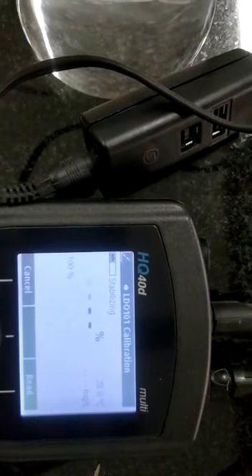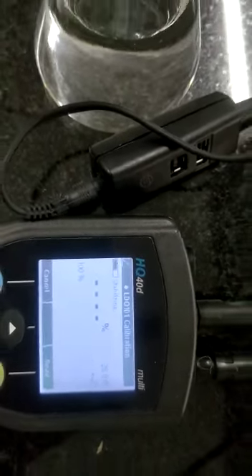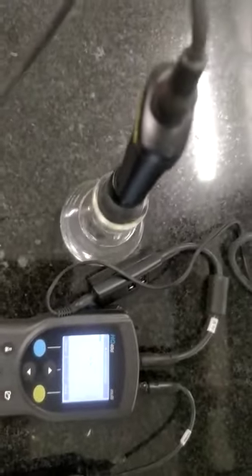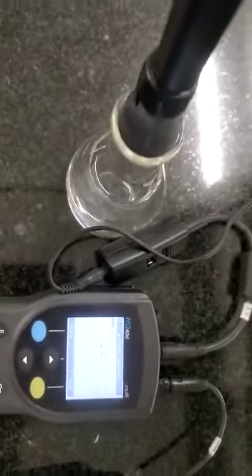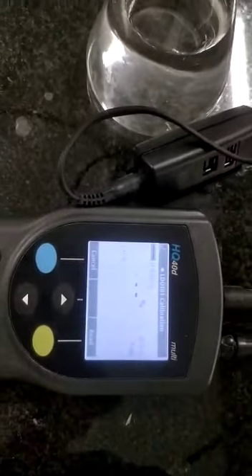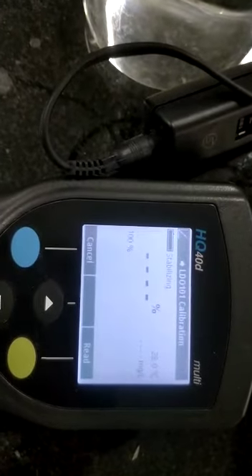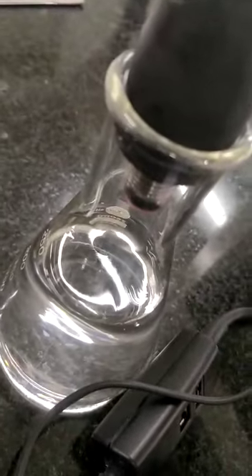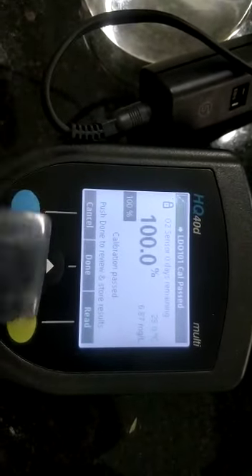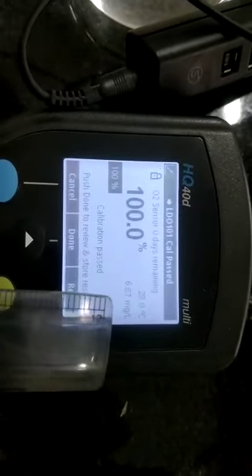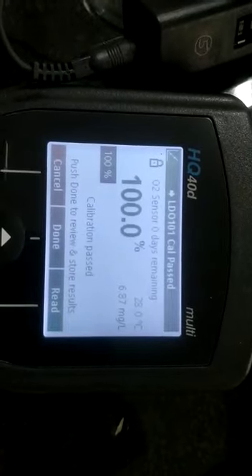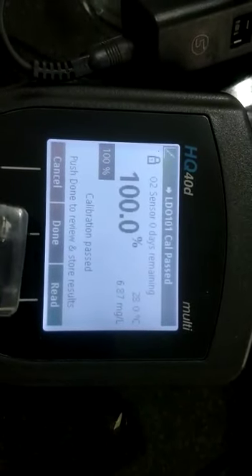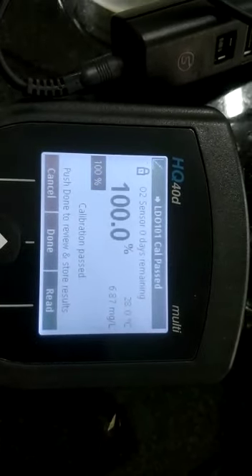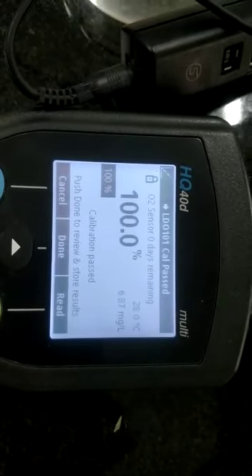At 100 percent saturation, you will get the value of DO along with the temperature. The indication of the DO is given when there is a red and blue blink in the sensor. On the DO meter at 100 percent saturation, you have a DO value of 6.87 milligram per liter at a temperature of 28 degrees Celsius. This was the step for the calibration.